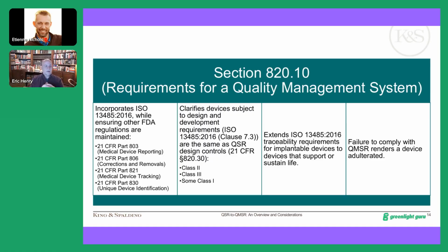Section 820.10 is where the FDA reiterates some quality management system scoping and linkage concepts with the QMSR. So first of all, it says that, yes, we have a new regulation 820, but don't forget, if you're a medical device company, you still have to comply with 803, 806, 821 as applicable, and 830. So MDRs, medical device reports, corrections and removals, medical device tracking for those companies that are subject to that requirement, and UDI. There will have to be some changes to references, with guidances and things that go with those, but those regulations stay in place and in force.